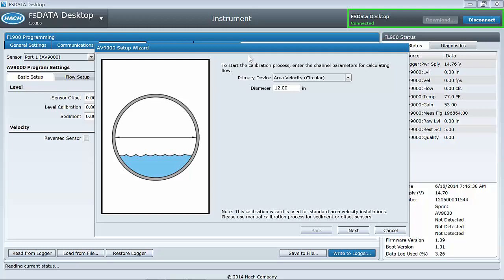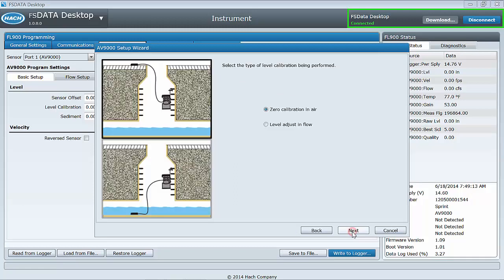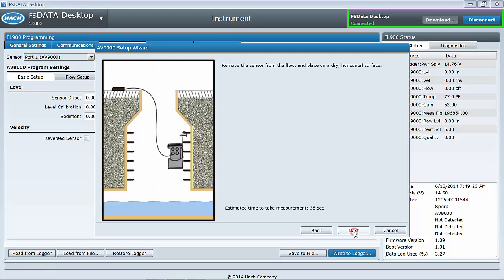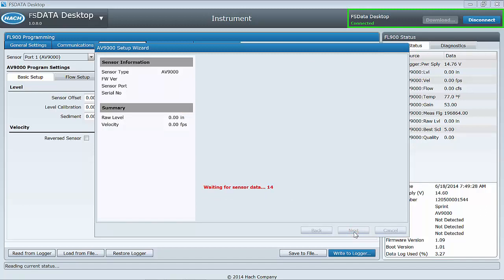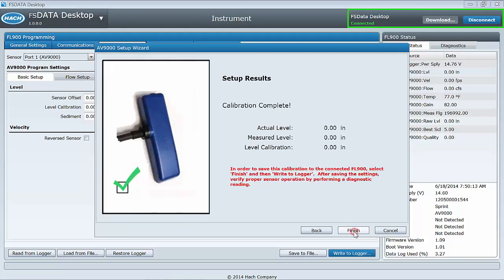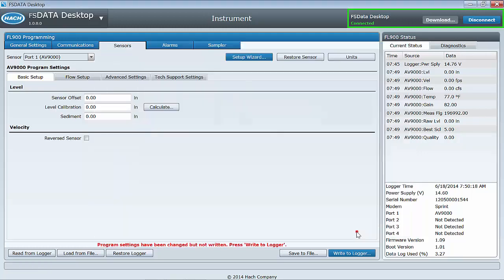Enter the flow settings by selecting the channel geometry and entering the appropriate dimensions. Select the method of calibration you would like to perform. The illustration depicts the choices. Select Next, and the instrument will force a reading. Select Retry to repeat if the level value displayed here does not closely match your physical measured level. Review the setup results. Click Finish, then write to Logger to complete the setup process.